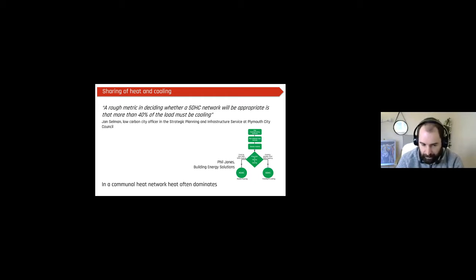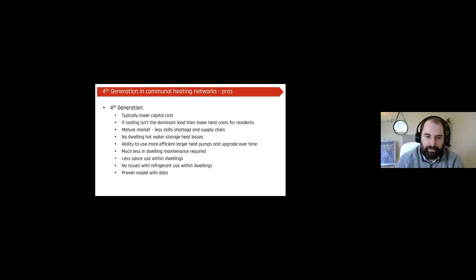But I'd make the point that in communal heat networks, heating, domestic hot water and space heating usually dominate significantly in the total load of the systems, and it's very uncommon that you see 50% cooling. Where that can happen in communal systems is, for example, if you have a mixed-use development and you could be connected to a supermarket or something, with a very tight contractual arrangement where they have high cooling loads, and you could potentially share those cooling and heating loads between the supermarket and the residential properties. So a quick summary of the pros of fourth generation communal heating.